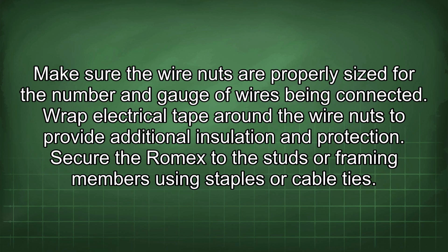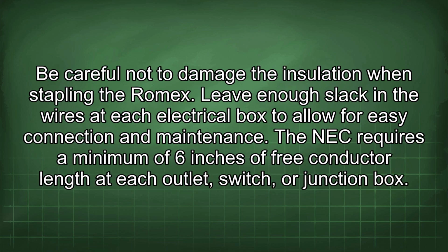Secure the Romex to the studs or framing members using staples or cable ties. Be careful not to damage the insulation when stapling the Romex. Leave enough slack in the wires at each electrical box to allow for easy connection and maintenance. The NEC requires a minimum of 6 inches of free conductor length at each outlet, switch, or junction box.